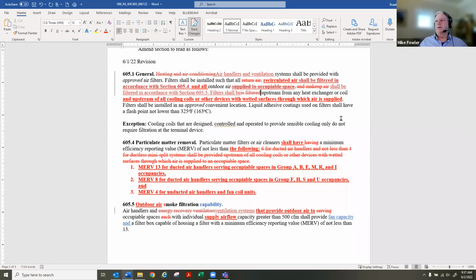I feel like it's getting away from the direction of where this was trying to go in terms of heated or cooled air. If outdoor air is feeding that heating or cooling system, that no longer has to be the MERV 13 filters. It was set up so heating and cooling recirculated air would be 605.4, and a DOAS system would be 605.5 with the capability. These recent edits have taken away any outdoor air supplied to a heating or cooling system. It has lost the MERV 13 piece as a requirement. It's only the capability.